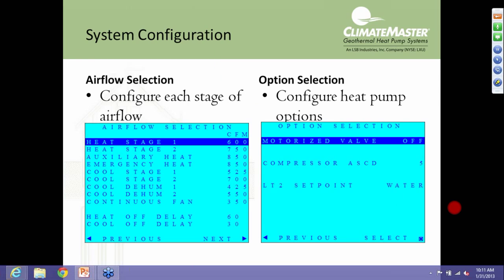So the default is this is turned off. You want to leave this off unless you've got that external valve installed. If you turn that on, nothing's going to happen to that heat pump until it sees that end switch feedback from that valve. And if that valve's not there, that's not going to happen.